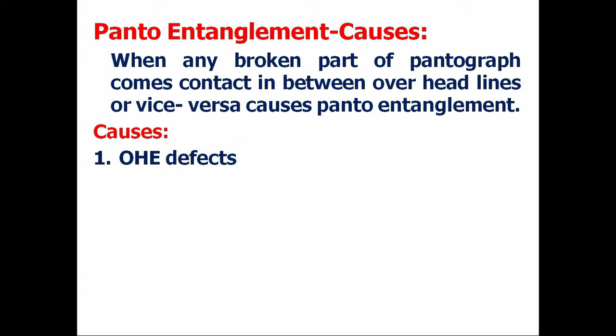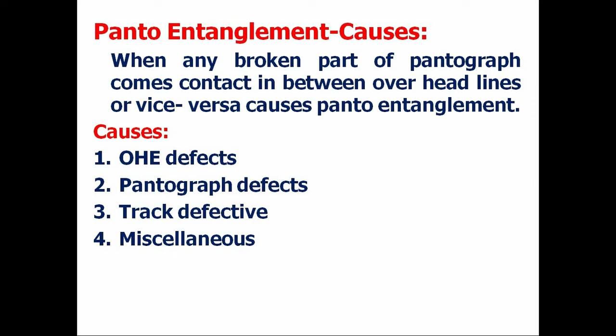So the various reasons for panto entanglement can be classified as OHE defects, pantograph defects, track defects, and miscellaneous. Now, coming to the OHE defects, the reasons may be damaged stay tube insulators. The cantilever assembly consists of stay tube, bracket tube, register arm, etc., that we will see later. Stay tube insulators may be damaged or broken, bracket tube insulators may be damaged or broken, cantilever assembly parts may be damaged or broken, or jumpers or droppers may be damaged or broken. So these are a few defects of the cantilever as well as the OHE parts.